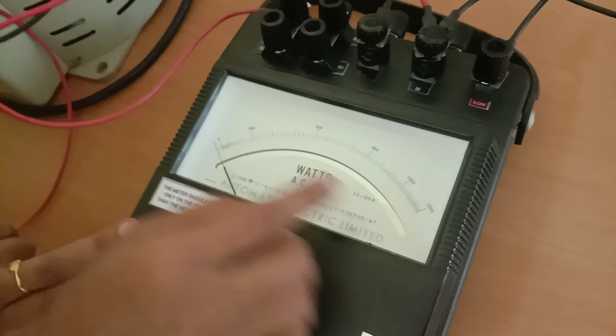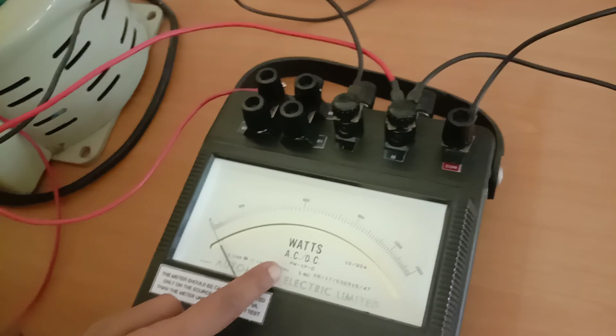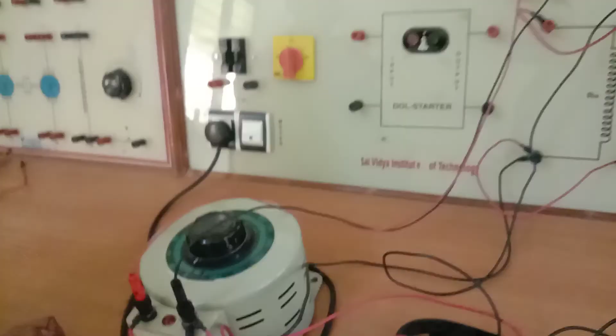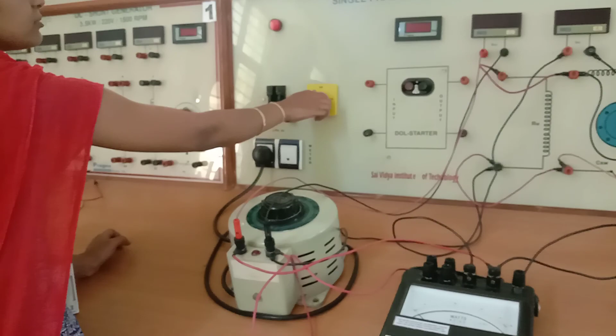And the K constant for this will be the voltage, 150, multiplied by 20, multiplied by the power factor, which is 1, divided by the full scale reading, which is 1500. Now let us switch on the circuit and apply the rated current.